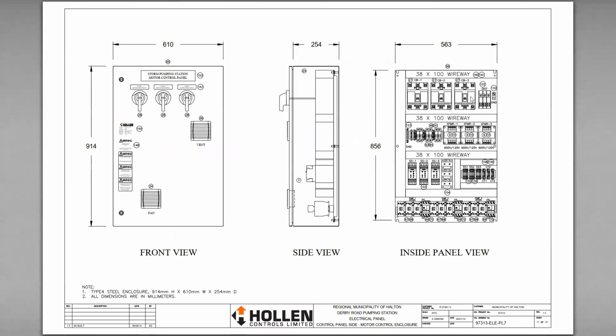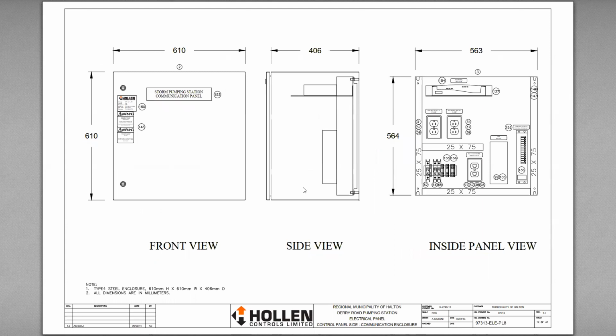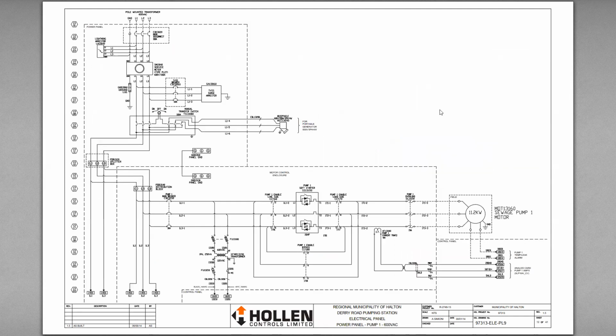This is the motor control panel. So you've got your main breakers, and you've got your soft starts. Sorry, this one doesn't have drives. It has soft starts, and then it has bypass contactors, not VFDs. Soft starts are similar to drives, but they only accelerate up to their speed. So they can't modulate their speed, but they will start slowly, which is better for the equipment. A bunch of internal panels, a networking panel.